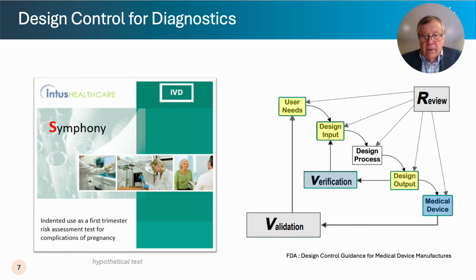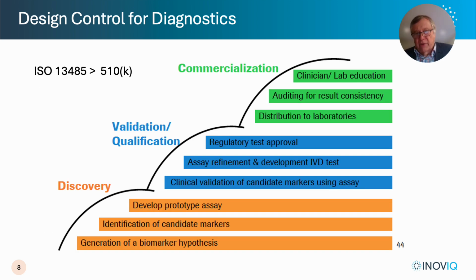Now the medical device can be validated against the user needs, asking the question, have we actually satisfied the criteria to deliver a first trimester risk assessment test for complications of pregnancy that performs with suitable diagnostic performance. And the whole process can be graphically summarized here into the discovery phase, the validation qualification phase, and commercialization phase. And this whole process is conducted within the framework of an appropriate regulatory standard, in this case, ISO 13485. And it's this information, the data obtained in the discovery, validation, and qualification phase, that is used to generate the regulatory certification application. And in this case, it was a 510K application.